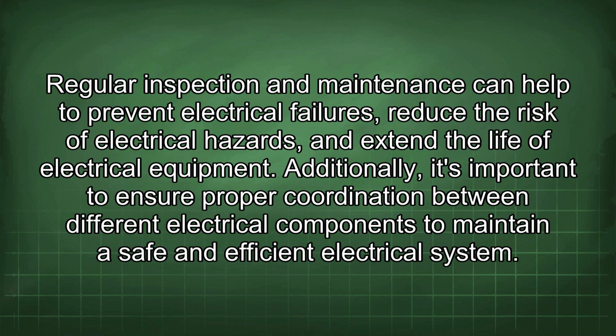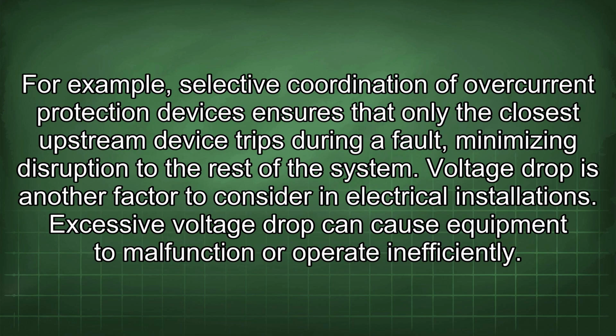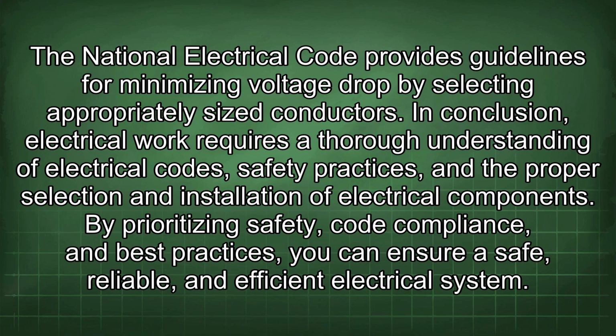Additionally, it's important to ensure proper coordination between different electrical components to maintain a safe and efficient electrical system. For example, selective coordination of overcurrent protection devices ensures that only the closest upstream device trips during a fault, minimizing disruption to the rest of the system. Voltage drop is another factor to consider in electrical installation. Excessive voltage drop can cause equipment to malfunction or operate inefficiently. The National Electrical Code provides guidelines for minimizing voltage drop by selecting appropriately sized conductors.